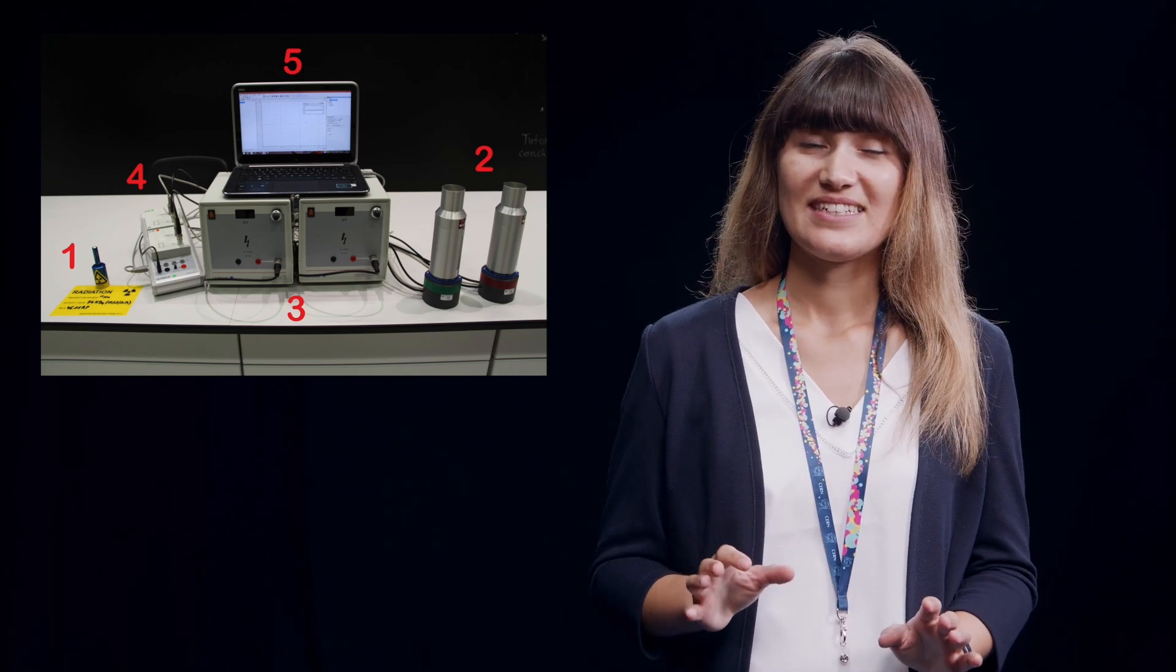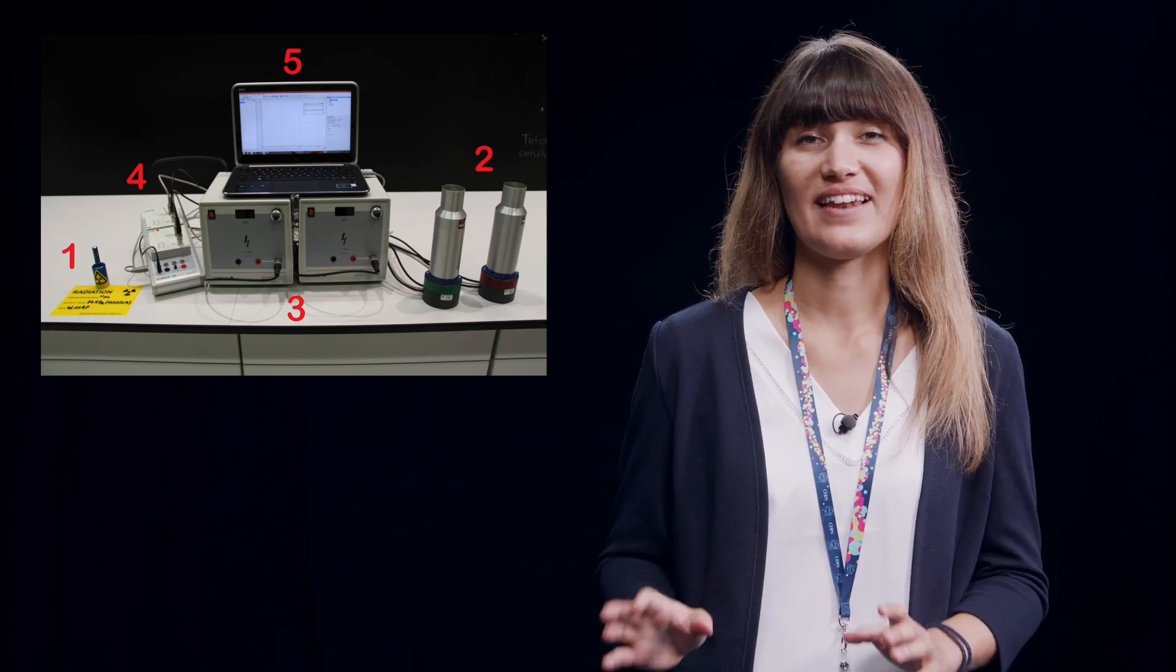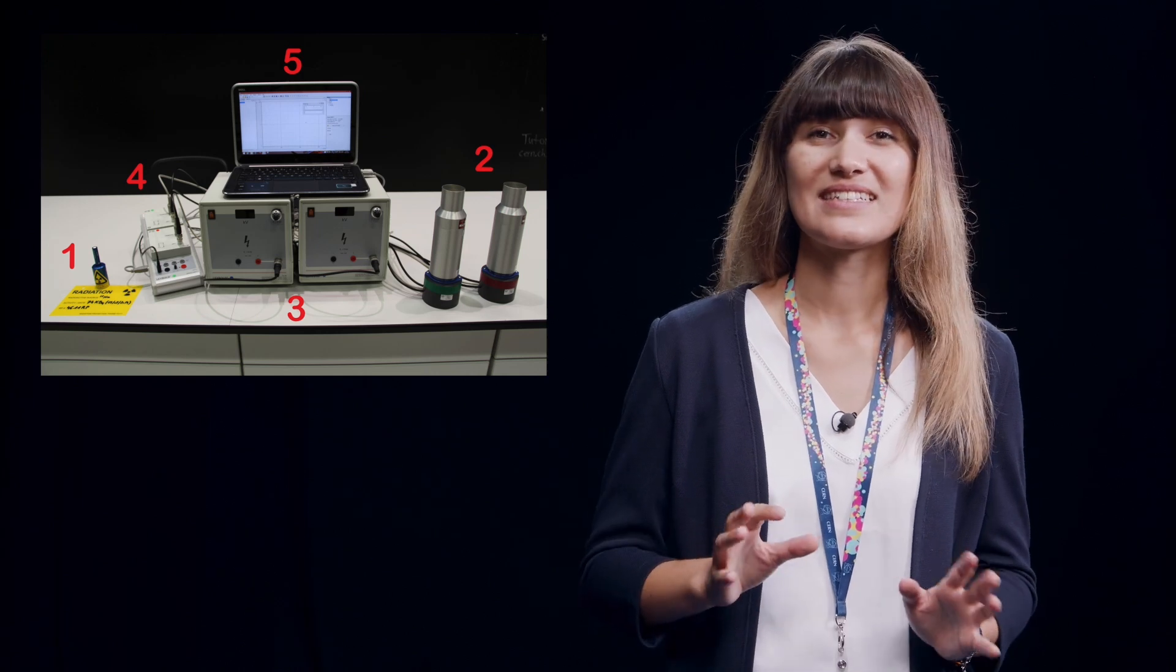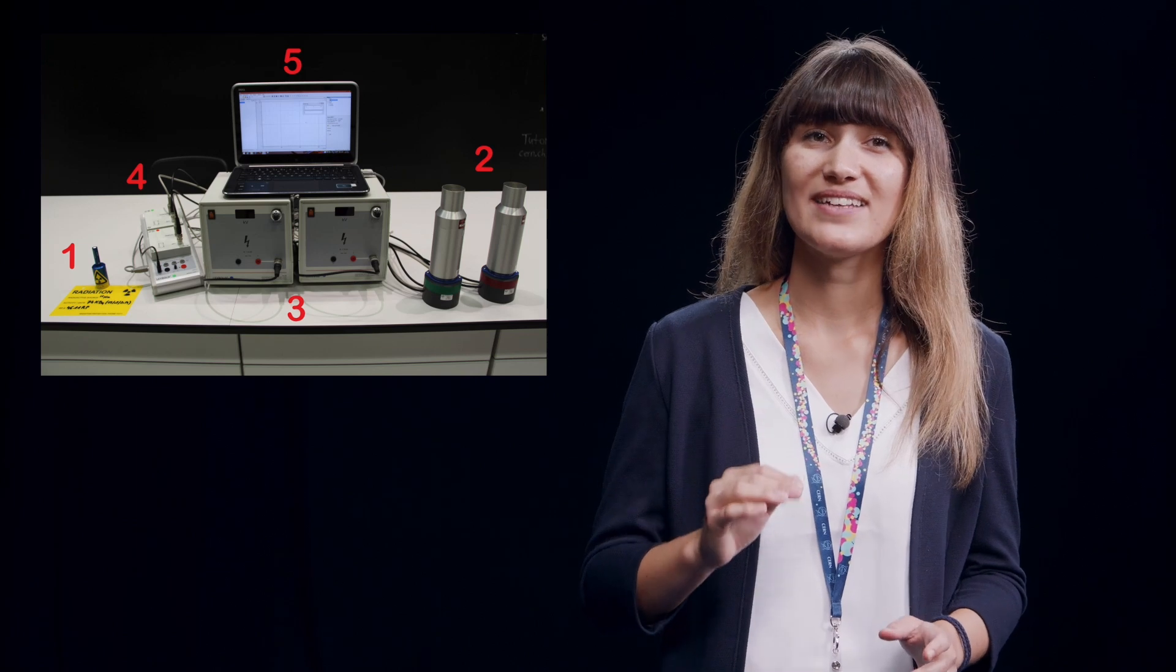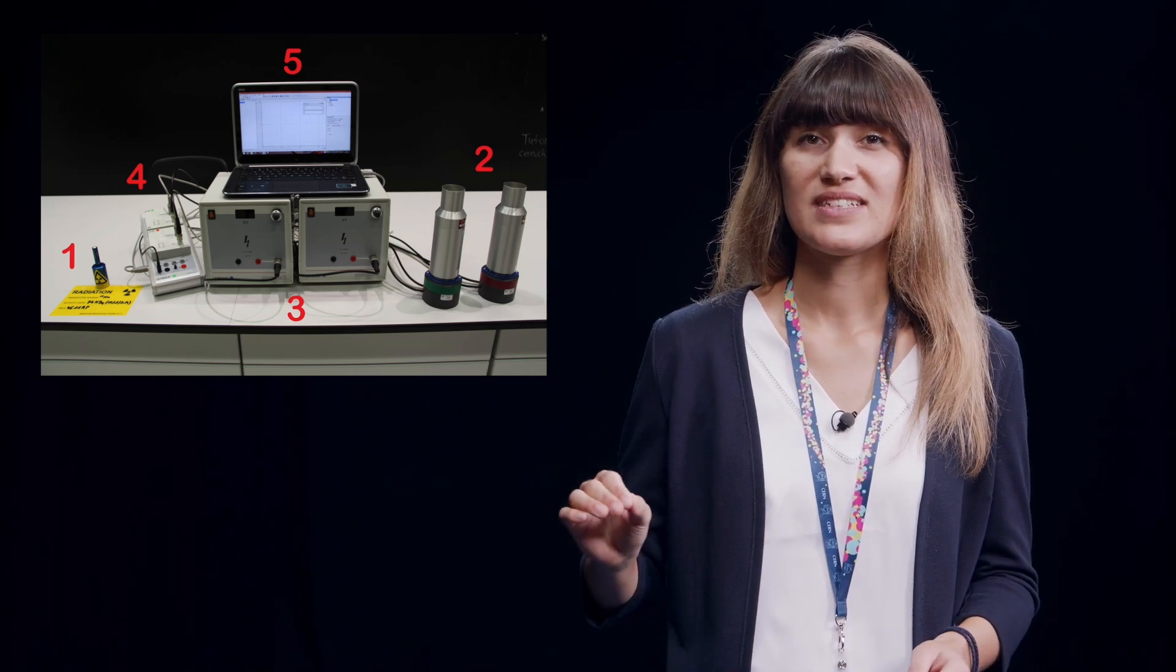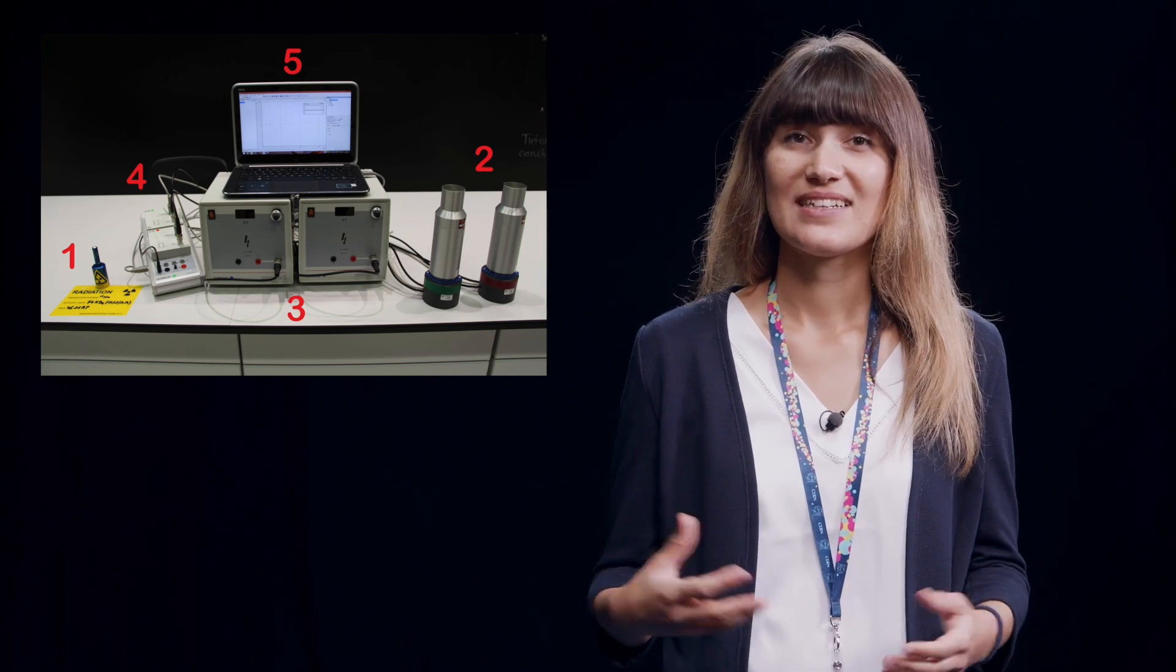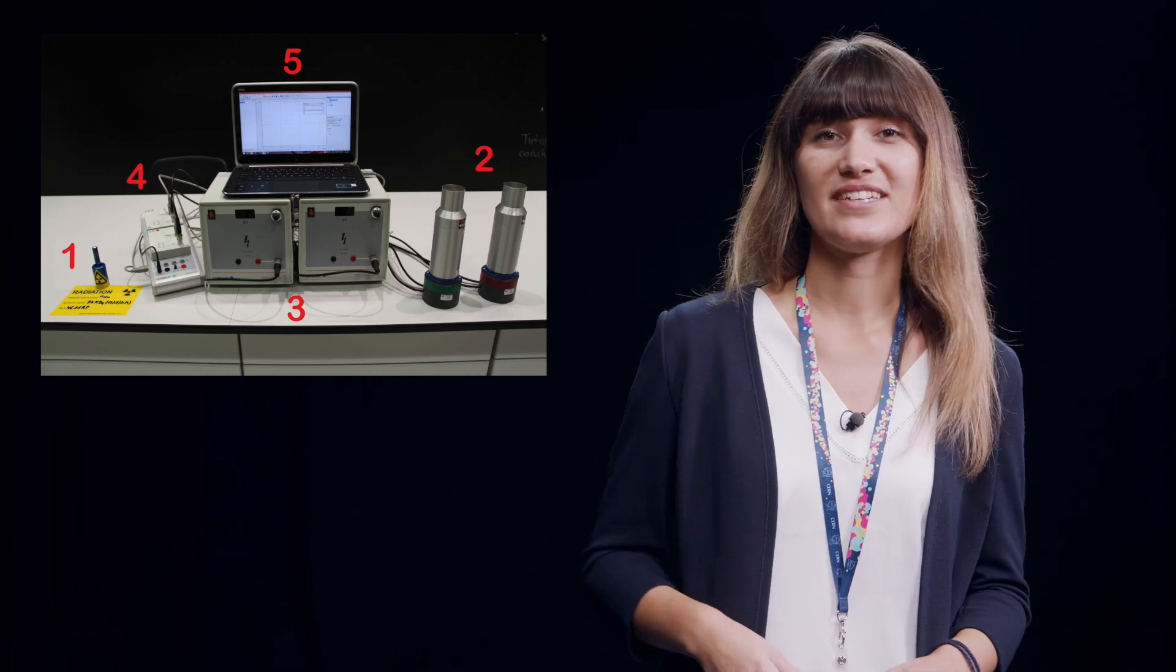The scintillation detectors are connected to a measurement interface with multichannel analyzer. In short, this is a device that sorts electrical signals according to their size into different channels. The number of the channel tells us how big the electrical signal was. This, in turn, tells us how big the energy of the photon was that moved through the scintillation detector.